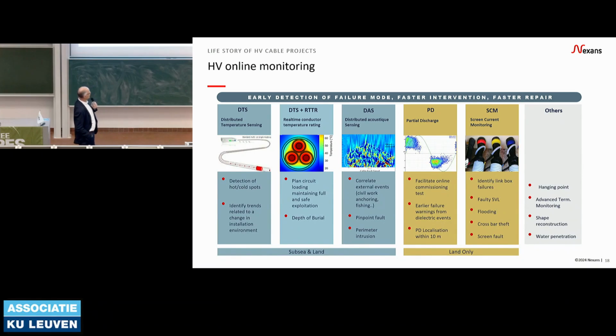Namely for the cable it's very useful. If you have, for example, cross-bonding inside your joints, you can check that the cross-bonding is still working, otherwise you have additional losses and unbalancing of your link. So all these kinds of things today can be checked by technical devices we include inside the cable to make up this whole system.